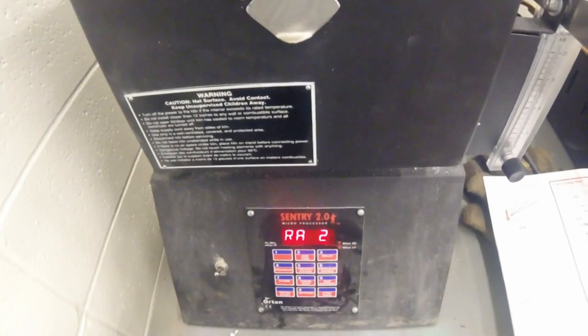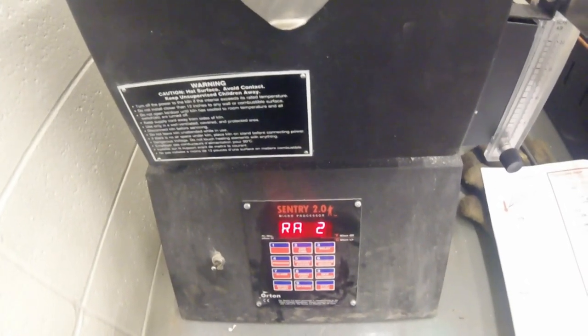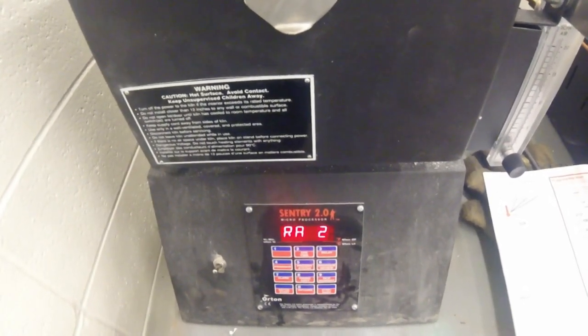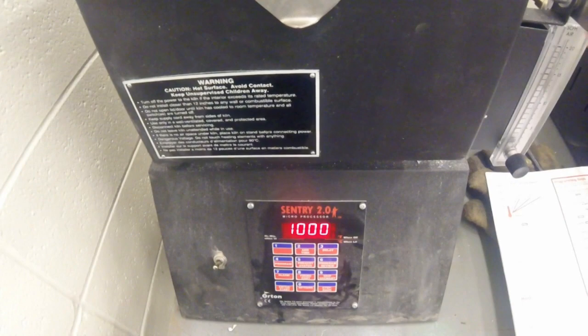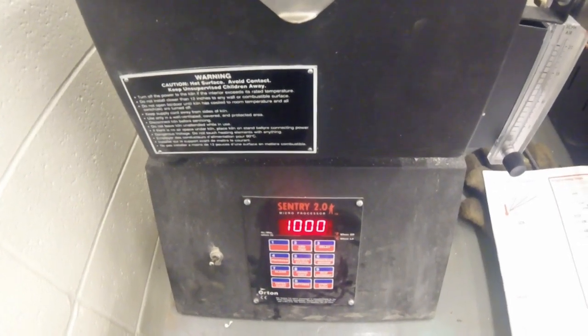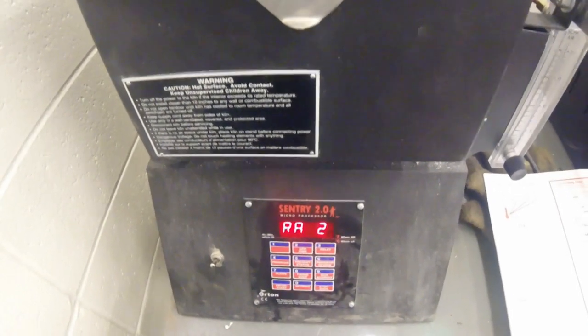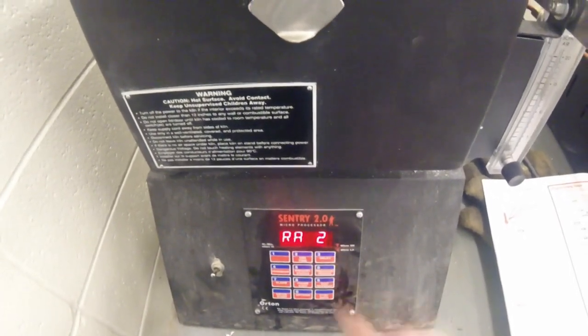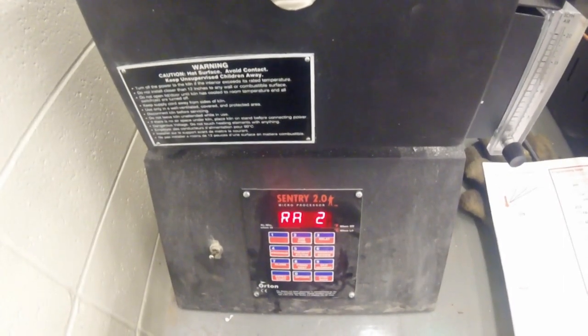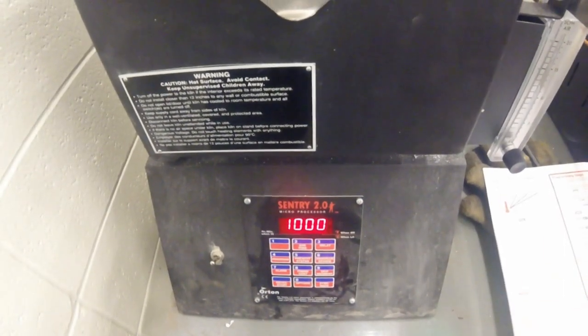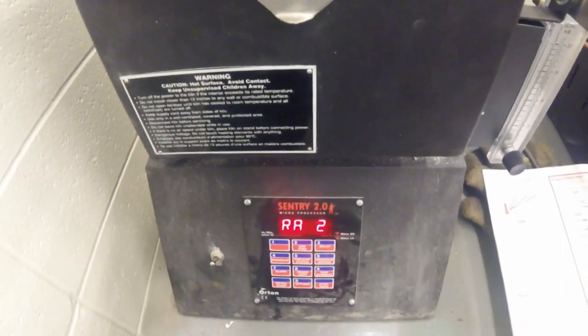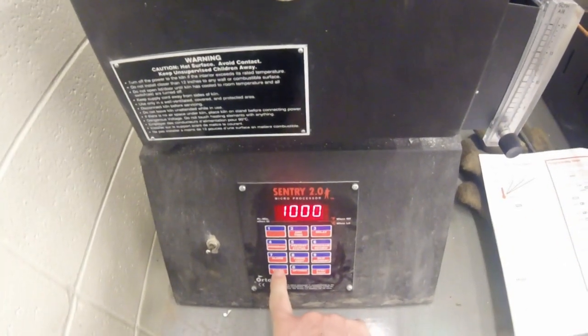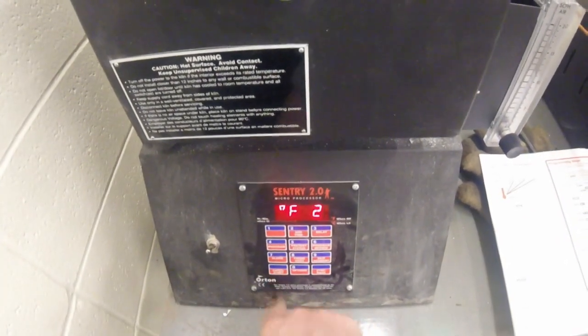RA2 is the same as RA1, which also stands for the firing rate for the segment, or the temperature change per hour. We will stay at 1,000 so that way our temperature does not rise above the desired temperature for heat treat. Hit enter.